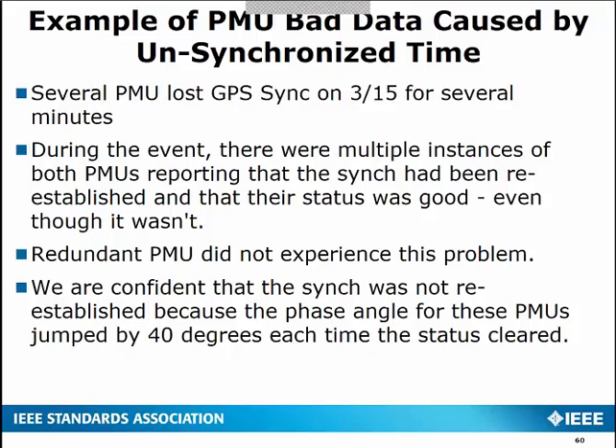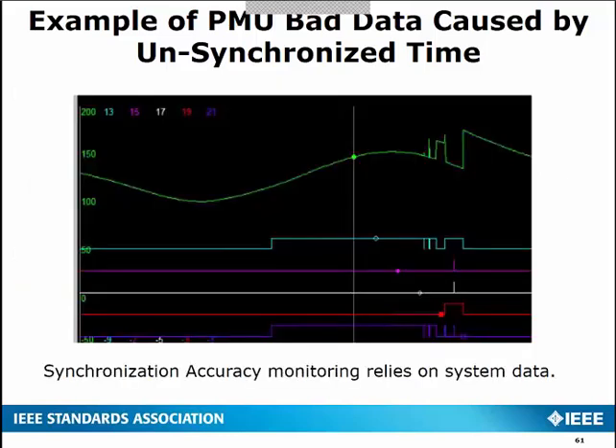We are confident that there was a sync problem because suddenly the angles of the PMUs jumped by 40 degrees. This is shown in the next slide. The green line is the angle jumping by 40 degrees. The aqua blue line is good sync, then loss of sync, and then good sync. And right when it says it has good sync at the end of it, that's when the angle jumps. So clearly a problem with the timing data on the system.